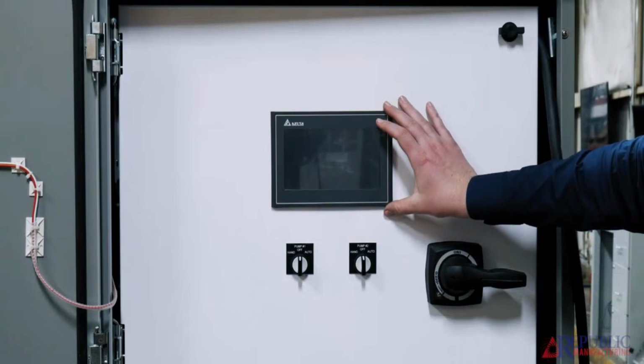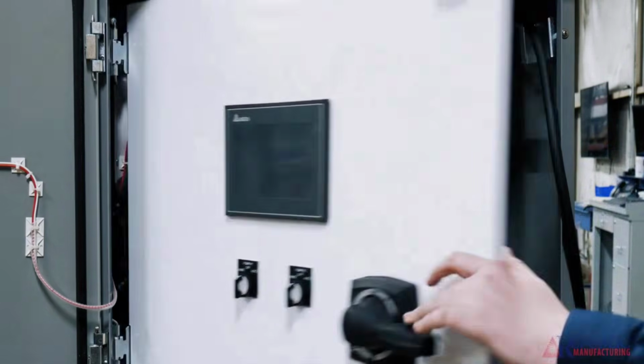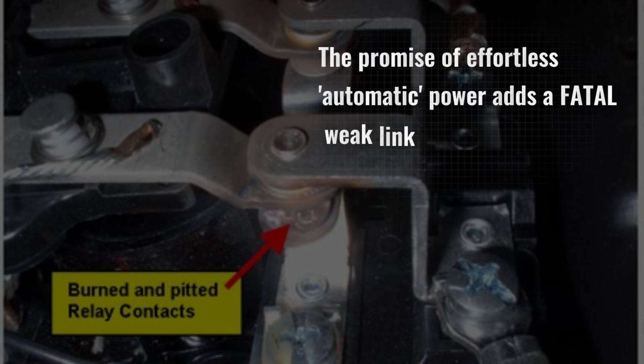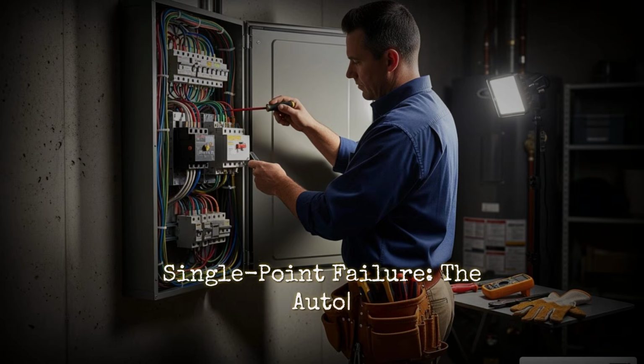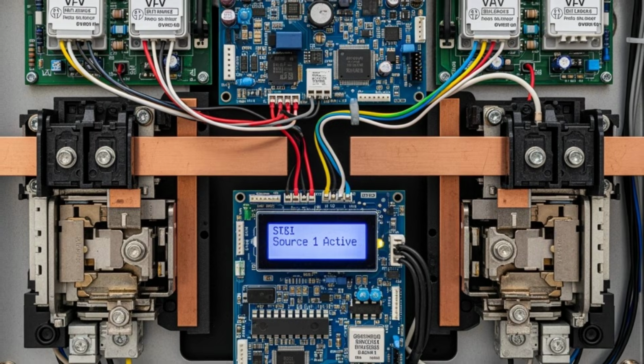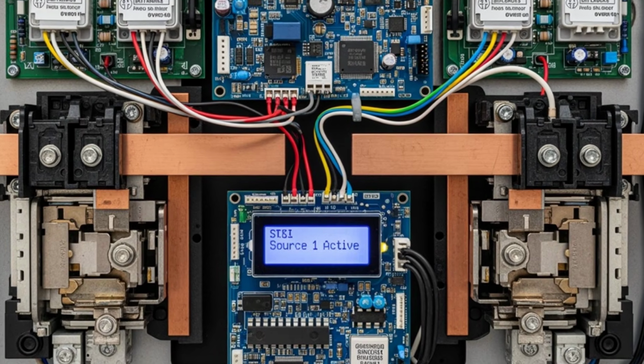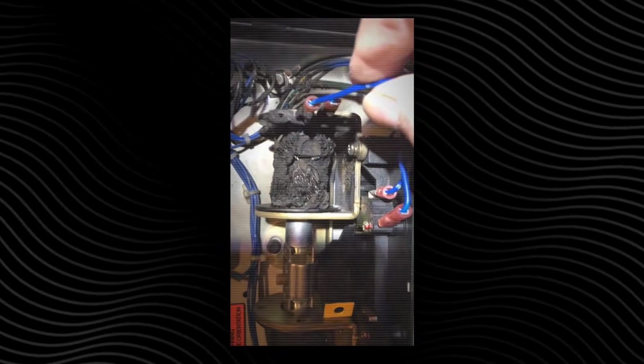But in the engineering world, every time you add an automated computer to a high-voltage mechanical system, you introduce a fatal weak link. The most devastating single point of failure in these expensive systems is the automatic transfer switch. This is the computerized brain mounted near your electrical panel that tells the house to disconnect from the dead grid and accept power from the generator.